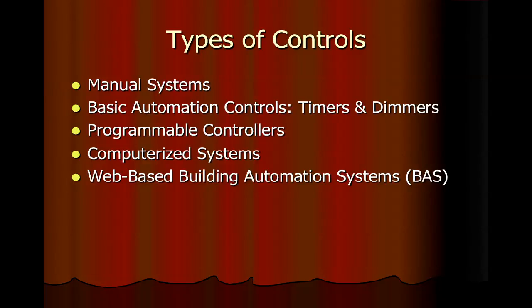That should be enough. Another thing to talk about are dimmers. Dimmers are a way of reducing energy, but unfortunately some dimmers only reduce the amount of light, but they don't reduce the amount of energy. They use what's known as a rheostat. So they take the entire amount of voltage and they divide it so that only a small amount of the voltage is going to the light bulb. The remainder of that voltage and current in the form of power then is going to be eaten up by the potentiometer itself, not doing any work for us whatsoever except actually providing a heat load in the light switch.